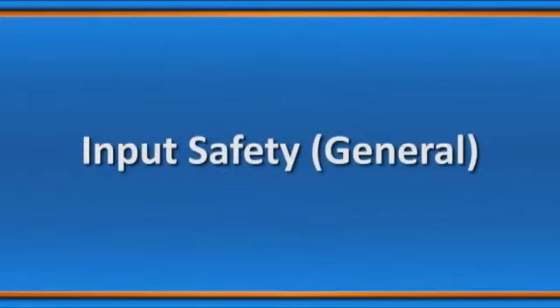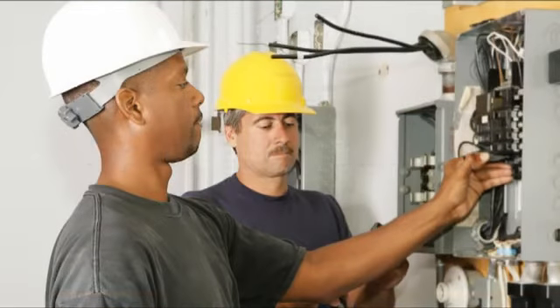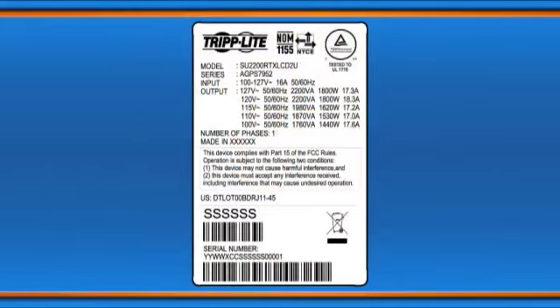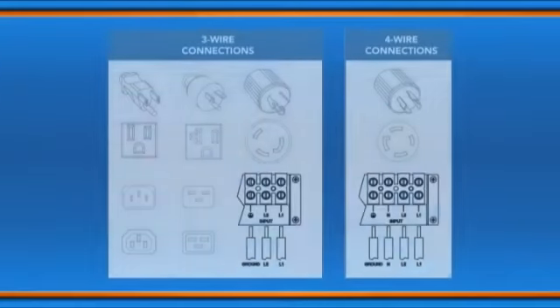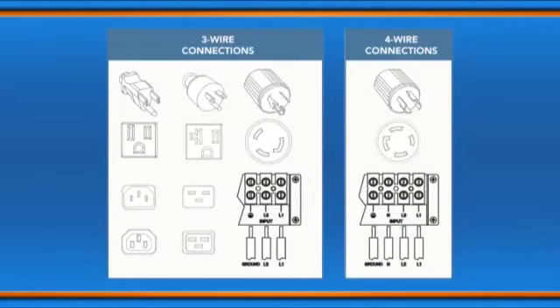The following safety warnings apply to both corded and hardwired models. The circuit that supplies power to the UPS must be single-phase. It must be grounded, and it must provide adequate protection against excess current, short circuits, and earth faults. Most UPS models are 3-wire: hot, neutral, and ground, but some models are 4-wire, including an extra hot. Check your model and ensure the circuit wiring matches.